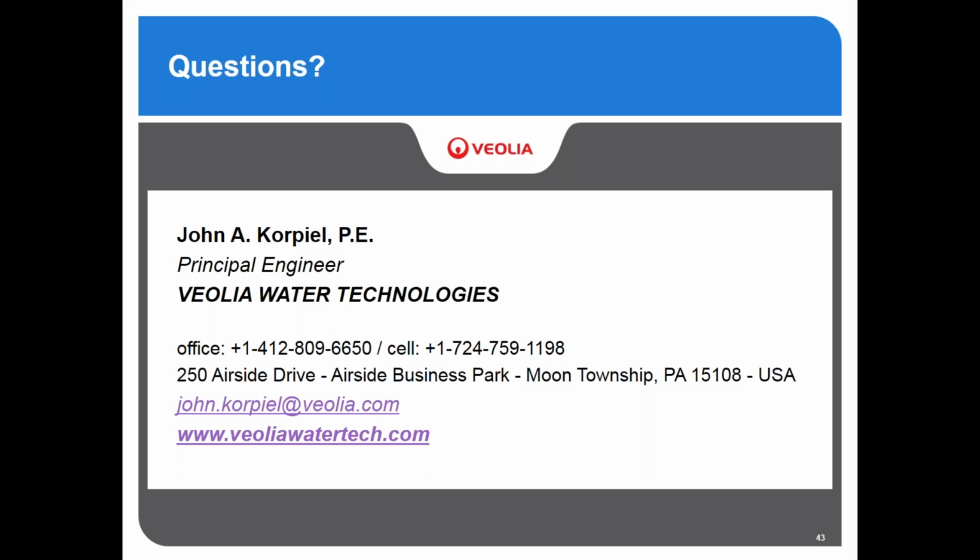Here's another one. What type of polymer do you use in multiflow? Well, for ROS applications, we found that we generally don't need to use polymer. Since the multiflow effluent is going to be further treated by the ceramic ultrafiltration, we find that it's actually good to have a little bit of solids in the carryover feeding the ceramic ultrafilter. It can easily handle that in cross-flow mode. So generally, when running multiflow in a ROS application, we don't use polymer. In a general application, if we didn't use ROS, we would consider using some anionic polymer. But in ROS, we find that polymer is generally not needed in the multiflow.